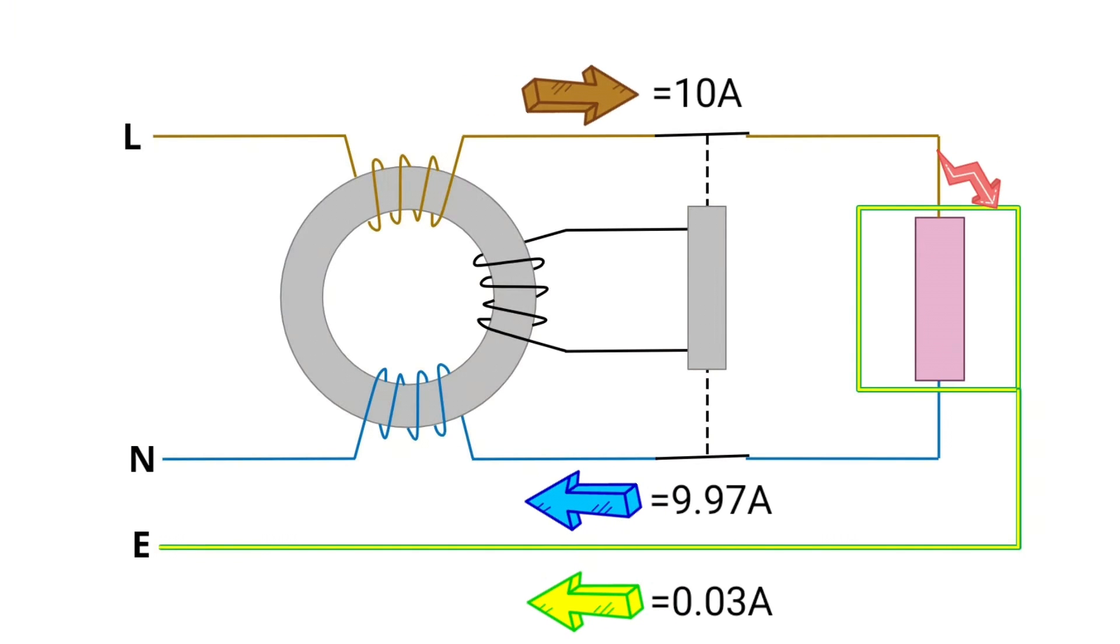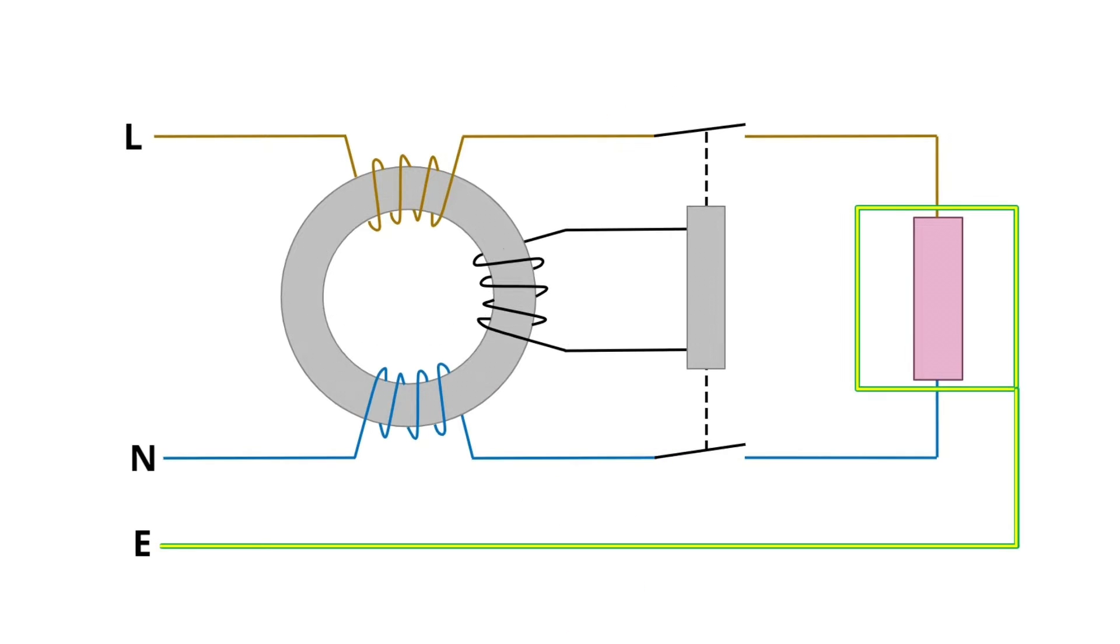Now, if an earth fault occurs and the current flowing back through the neutral is slightly smaller, this makes the neutral magnetic field slightly weaker than the one around the line conductor. So now this slightly stronger magnetic field is able to generate a small amount of current into the tripping coil using the exact same principles as the operation of a transformer. If the difference in current in the line and neutral is big enough, the current generated in the tripping coil will be enough to trigger the tripping device and disconnect the circuit.